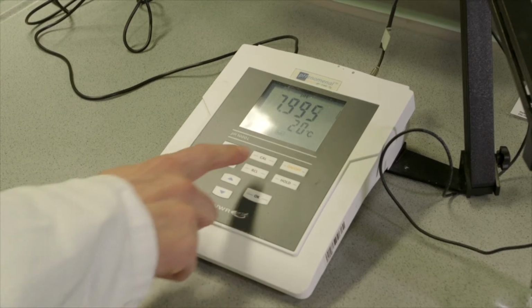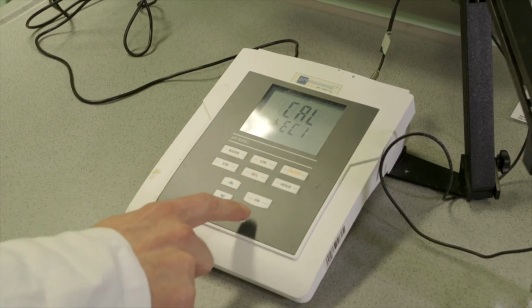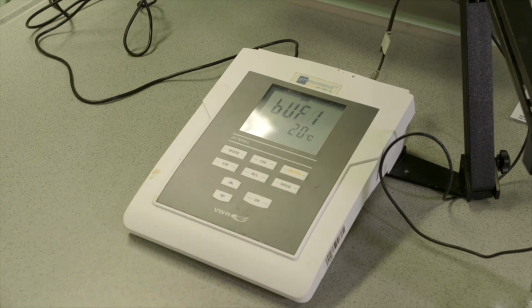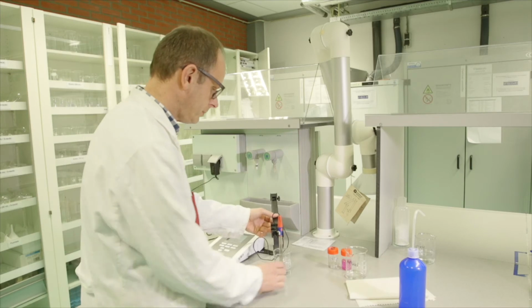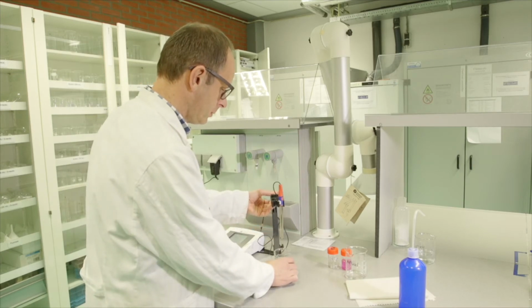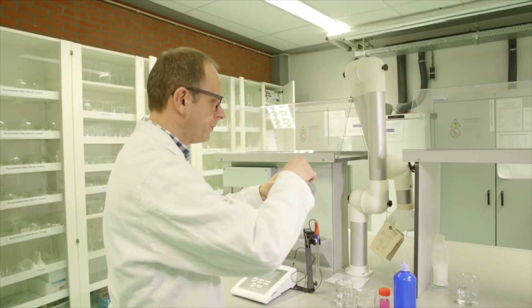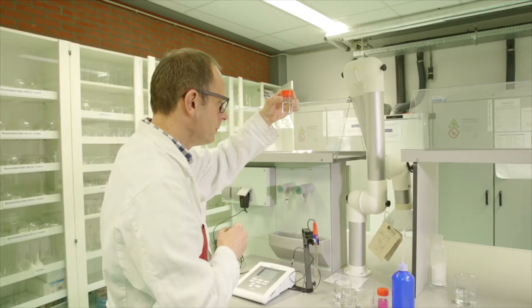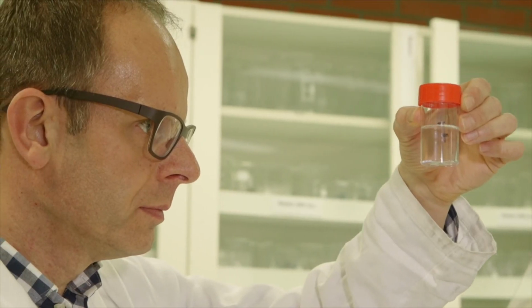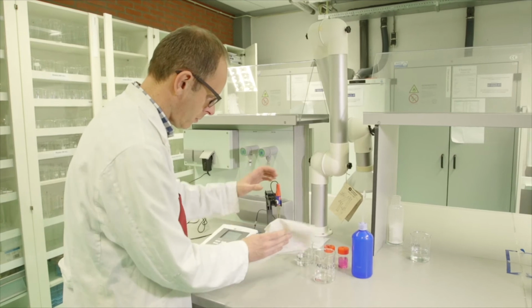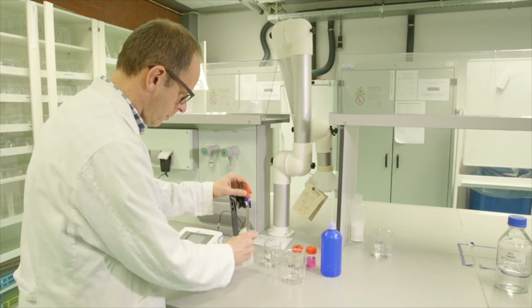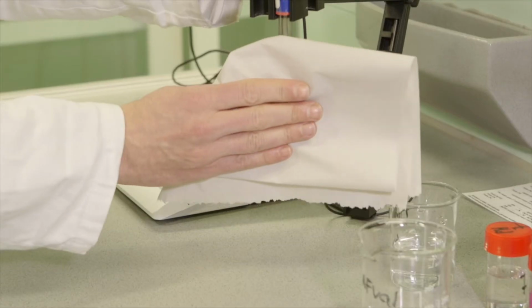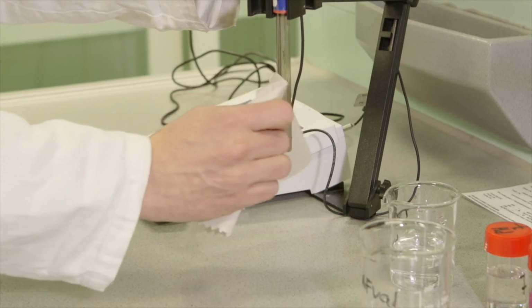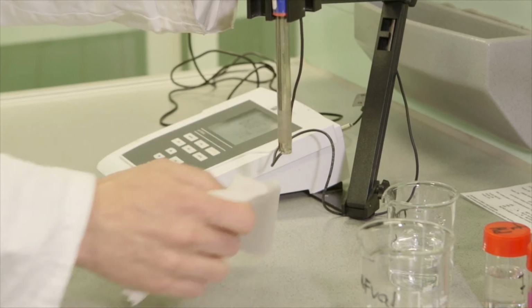To start the calibration, press the Cal button and then click OK. The device then requests if the electrode is in the first calibration buffer. We use the buffer with pH 7. Check the buffer. If there are particles floating in it or the colour is strange, discard the buffer and take a new one. Gently pat the electrode dry with a clean cloth before you place it in the buffer. Do not rub with the towel, as this can create a static charge which will interfere with the measurement.